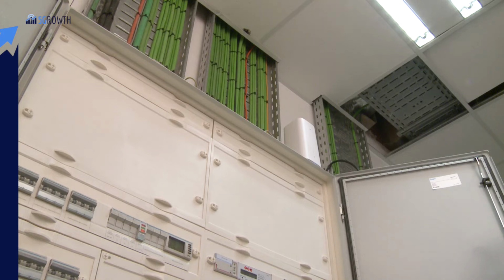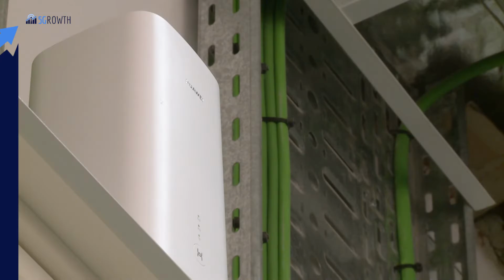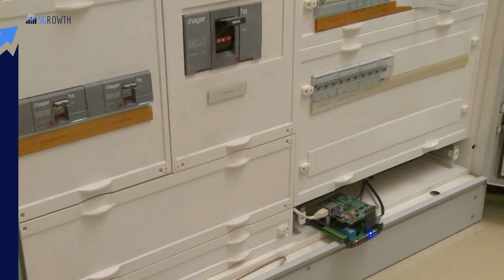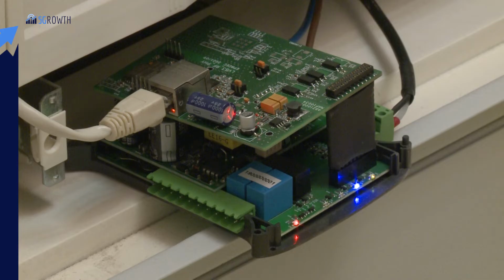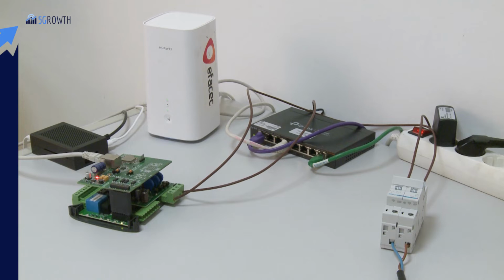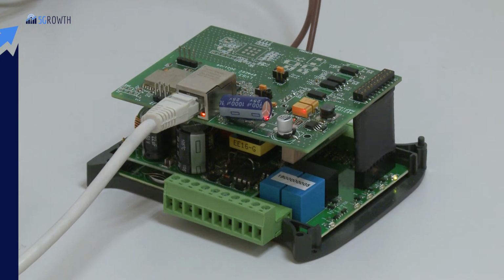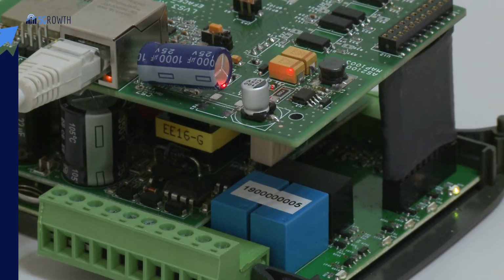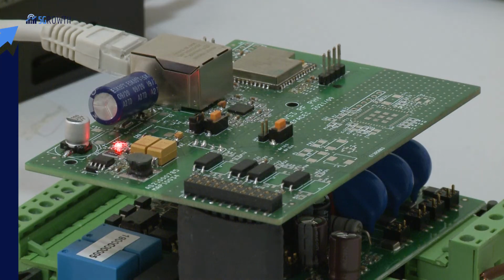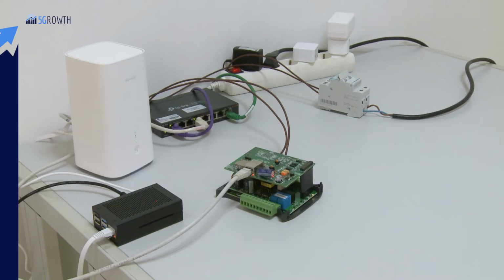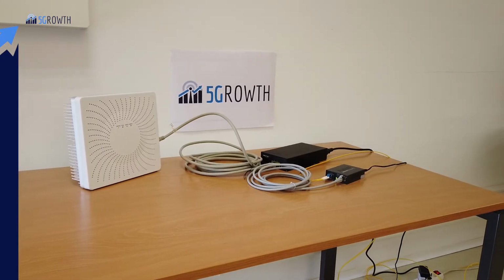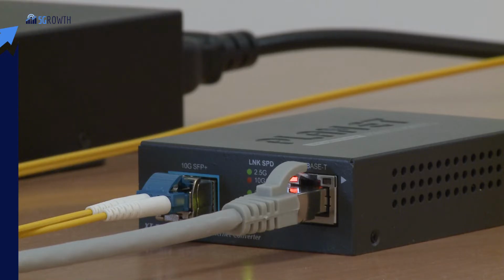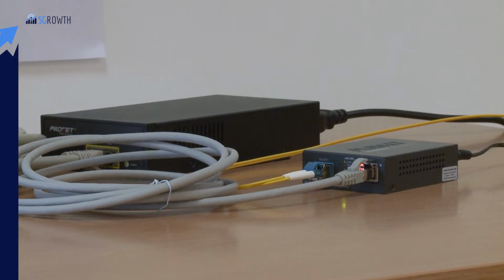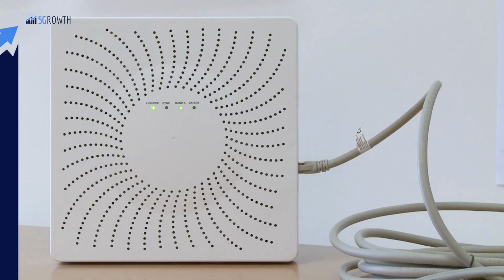In the second use case demonstration, we'll see how a power down incident in the low voltage distribution network is handled and transmitted to the control center. For that purpose, a power cut is simulated, affecting the electrical switchboard and interrupting the power supply of the low voltage sensor installed there. The voltage drop triggers the last gasp signal in the low voltage sensor. This signal is pushed into the 5G network to be acquired by the substation concentrator and immediately transmitted to the control center over the 5G radio connection.